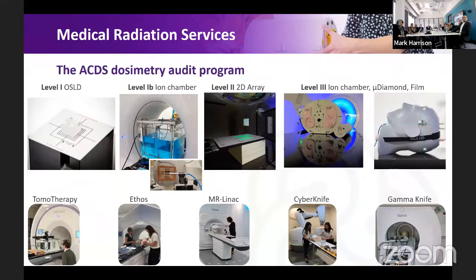And as we move across the right, we go to what's called a level 1B, which is a highly precise measurement in the water tank. We go to a level 2D array, which is a set of irradiations performed by the facility. They map that on their computer planning system, utilizing a CT dataset designed by and sent out by ARPANSA, which tests the capability of the planning system and the linear accelerator to deliver fields which ARPANSA has, again, put together, often from IAEA recommendations, to tweak out and tease the potential performance issues in the system.